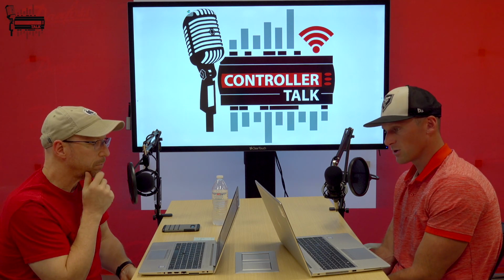It's just a single suction group pack controller, so if we are talking CO2 and it's a booster system, you would need at least 2 of these, one for low temp, one for medium temp. If we get into parallel compression, you could need a third. We've got better options for that today, but if it's the 781A, it's a single suction group pack controller. It can do up to 10 compressors in that suction group, 8 condenser fans. They can be on-off controlled or variable speed.